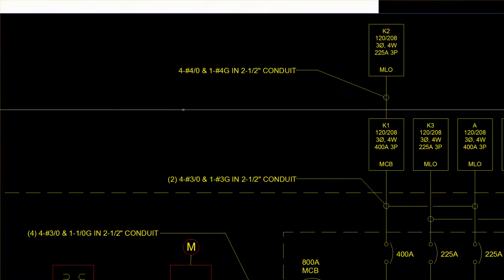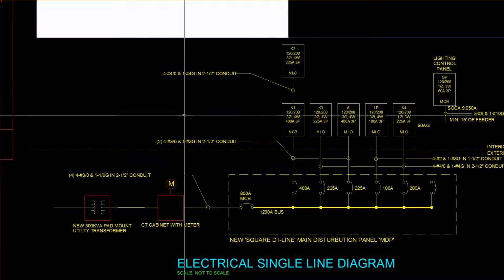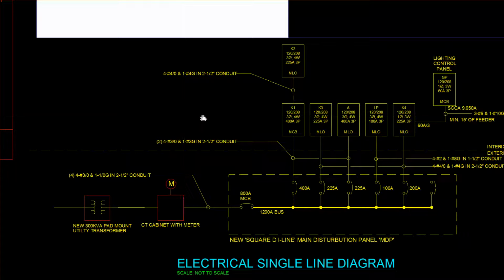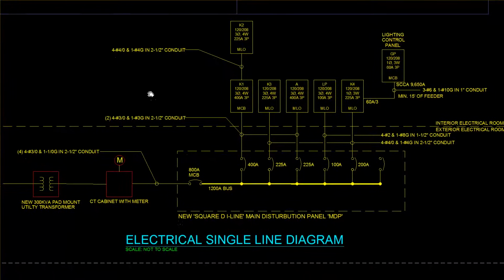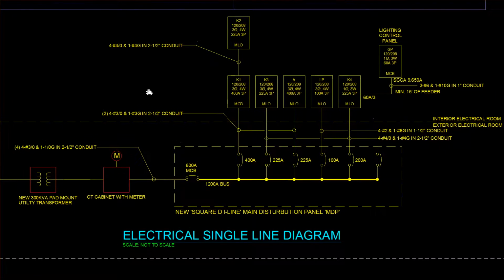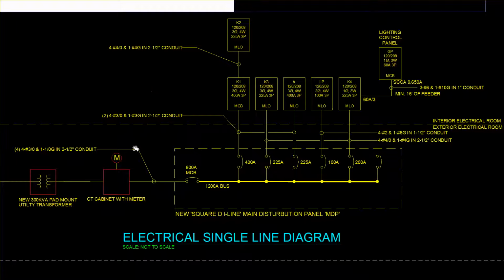It is commercial. It is for a restaurant, and so it has more detail in it. And so let me show you kind of the components here. Just going through this as quickly as possible. I don't want this to be as long a video as some of the others can be, but what you'll see, this is the utility transformer, and that's going to be provided by your local electric utility. This one is a larger service, 800 amps, and so you'll have a CT cabinet where the metering CTs, or current transformers, go to feed the meter.